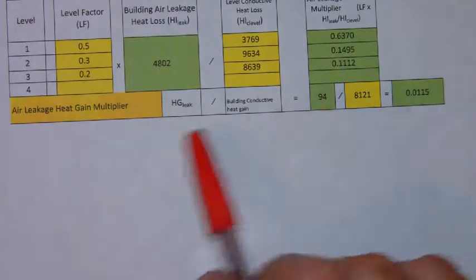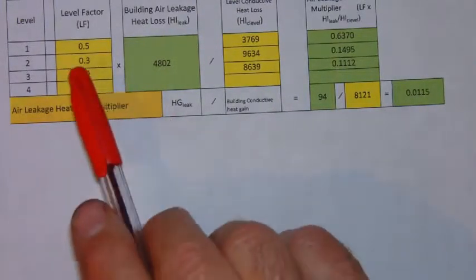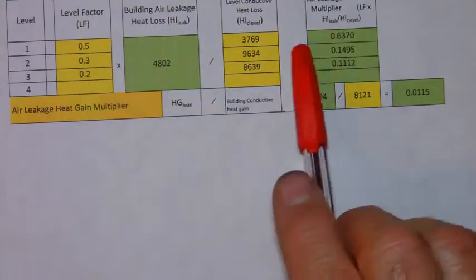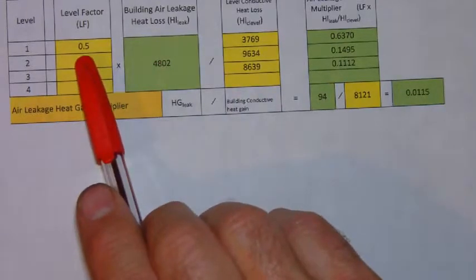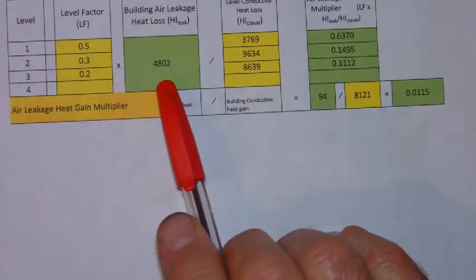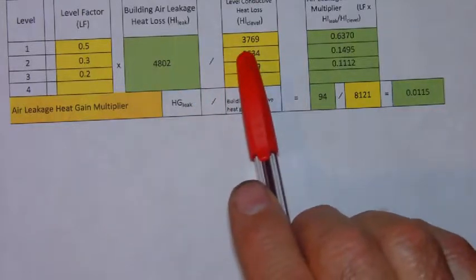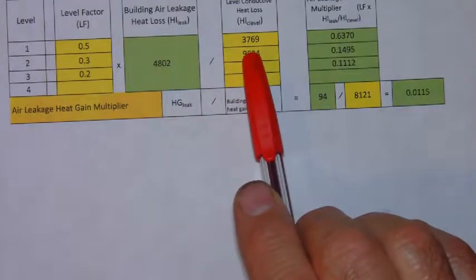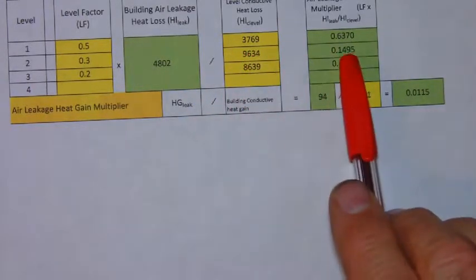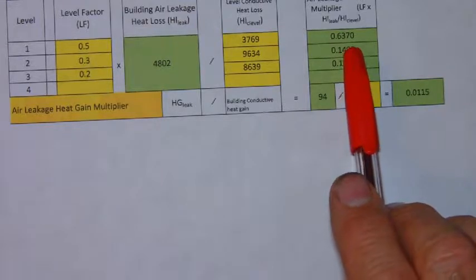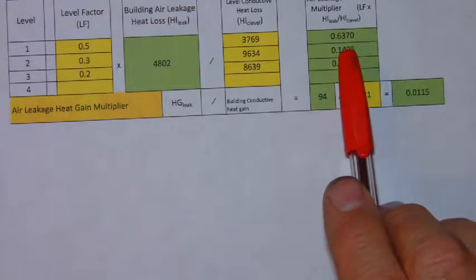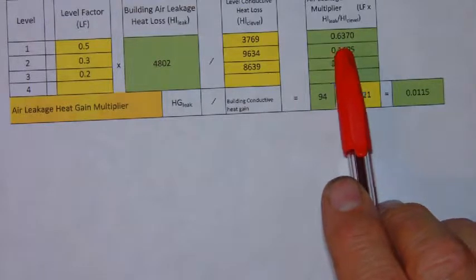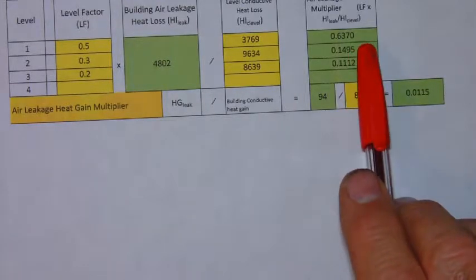The equation works like this. You take for level one you're going to take 0.5 times 4802 divided by 3769. That gives you a heat loss multiplier of 0.6370 and you want to carry four decimal places here.